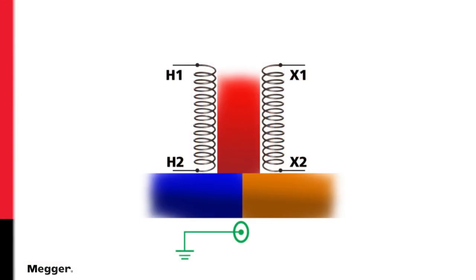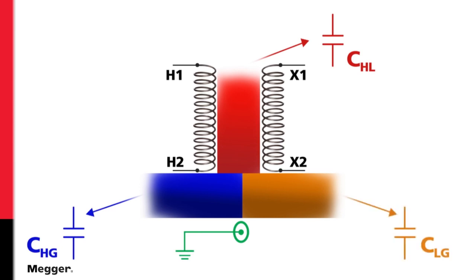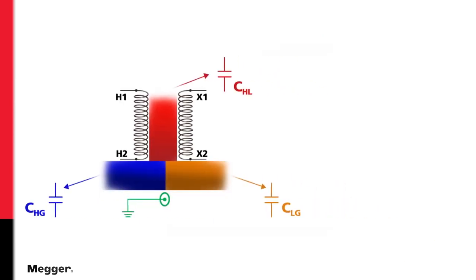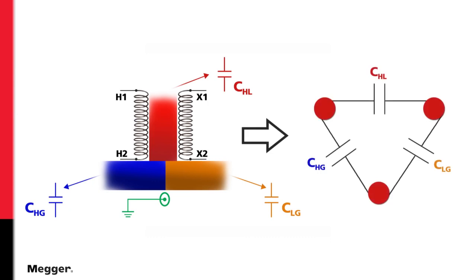For a typical two-winding transformer, we are interested in three key insulation measurements: high winding to low winding, high winding to ground, low winding to ground. Some newcomers to this test assume we test between phases, but it is between windings where test is conducted, as well as winding to ground.